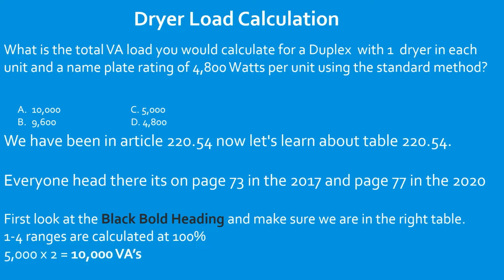So first we have to total them, but we have to remember, if you look at our question, these are only 4,800 watts, but I need you to commit to memory that when you're dealing with the standard method, dryers must be calculated at a minimum of 5,000. So we take that 5,000, we multiply it by our 2 units, and that's going to give us 10,000 VAs. And we're going to select A.